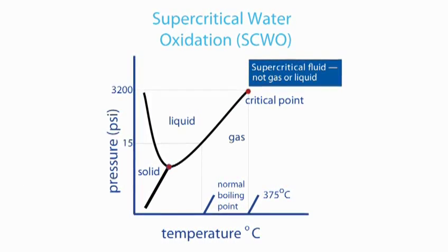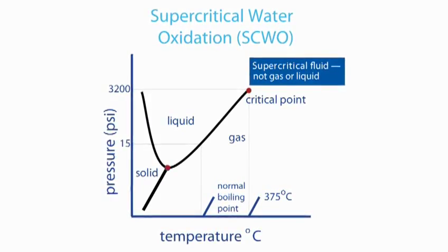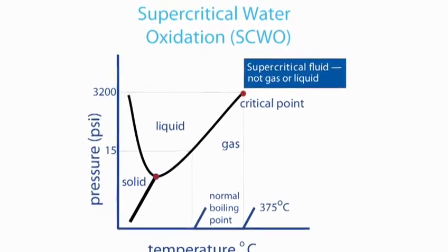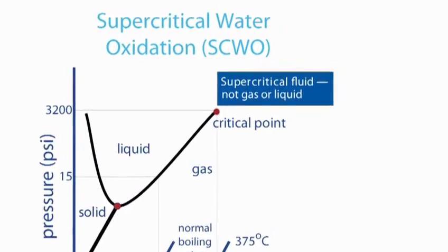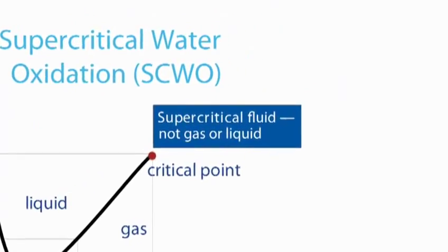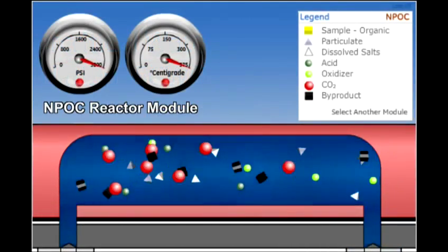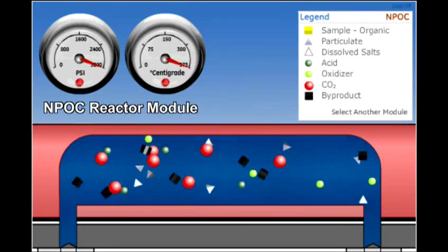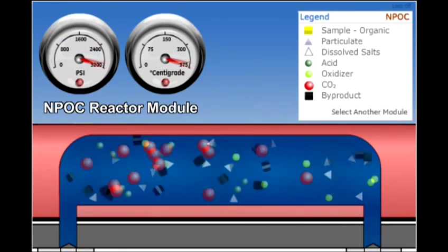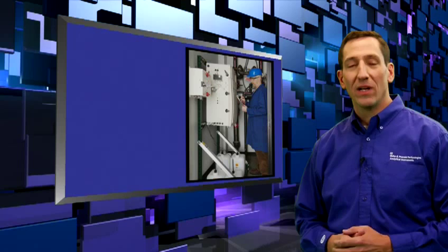By raising the temperature and pressure, the Innovox converts aqueous samples to a supercritical water phase. That lets the Innovox handle a wide variety of sample matrices. After each analysis, the Innovox removes troublesome particulate residues and oxidation byproducts from the sample flow path.